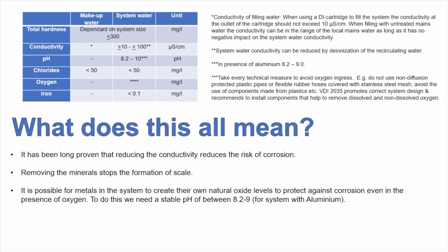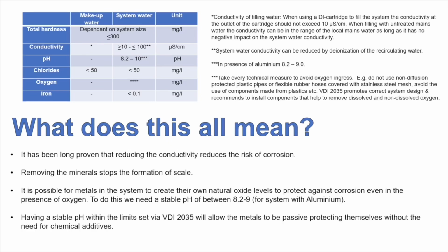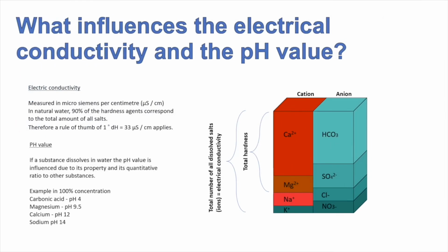To do this, we need a stable pH of between 8.2 and 9 for systems with aluminium. Having a stable pH within the limits set via VDI 2035 will allow the metals to be passive, protecting themselves without the need for chemical additives. What influences the electrical conductivity and the pH value? The table here shows that we've got cations and anions. These are our minerals within the water. They have different charges, so the minerals are what give us our electrical conductivity. By removing these minerals, we reduce the conductivity because we've got rid of the positive and the negative charges.